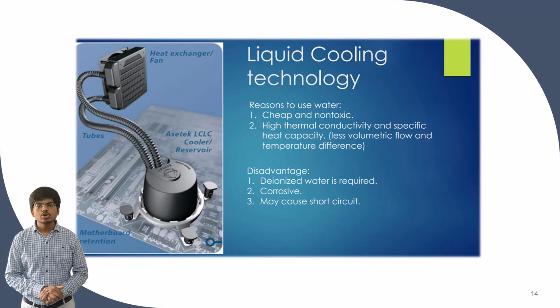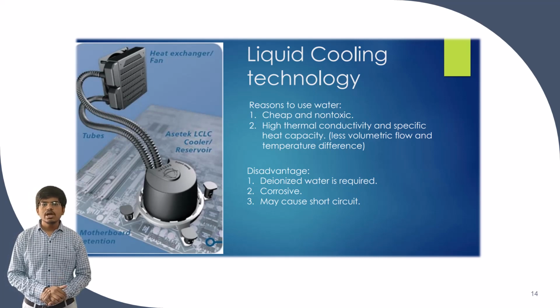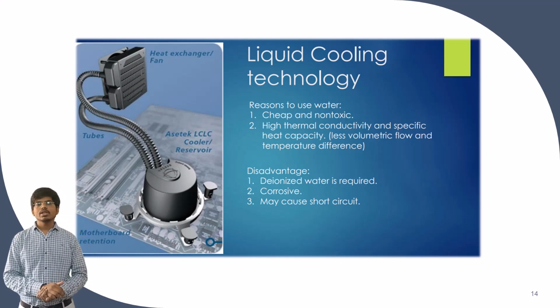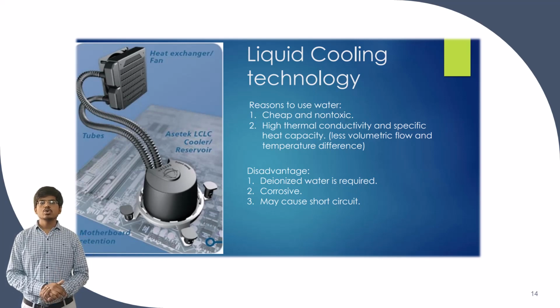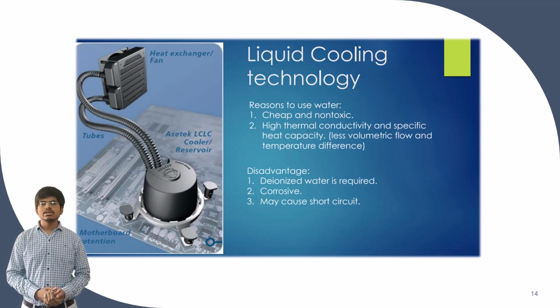Now, reasons to use water as cooling liquid are as follows. It is cheaper and non-toxic. It has high thermal conductivity and specific heat capacity. And disadvantages of its use are the requirement of deionized water, which is not cheap. Water causes corrosion in presence of air, and it may cause a short circuit as ionized water conducts electricity.